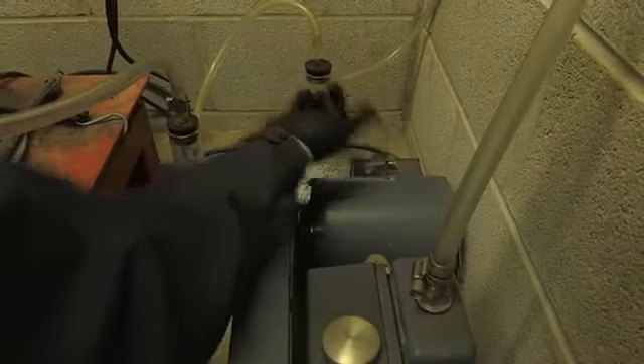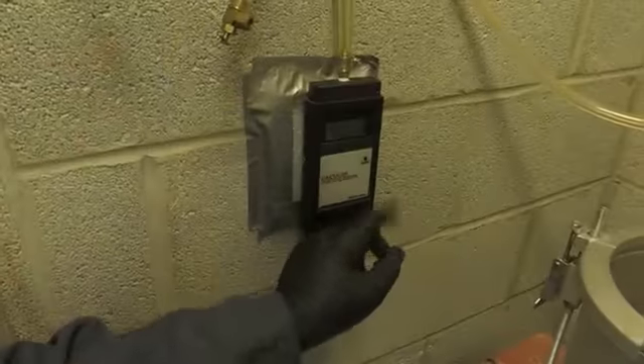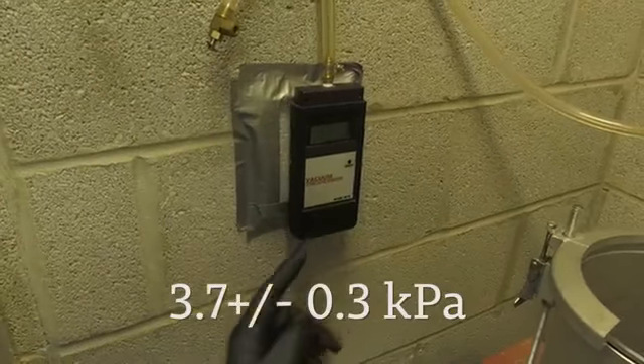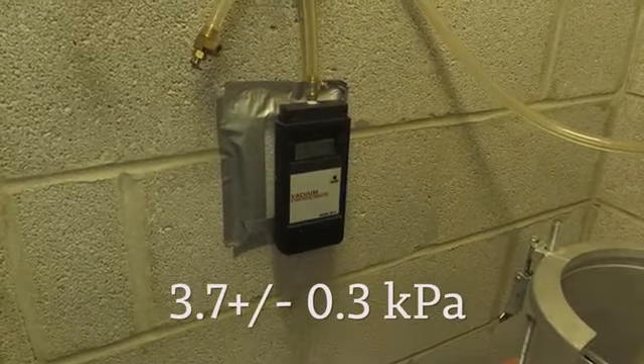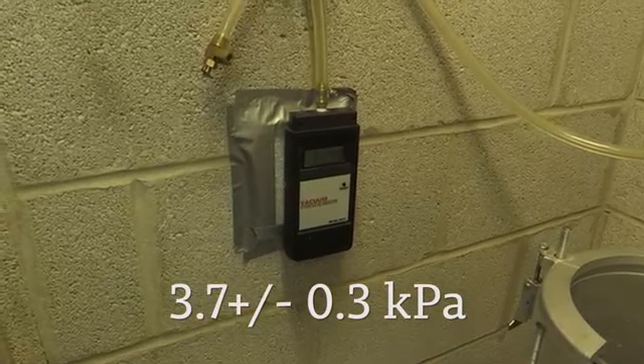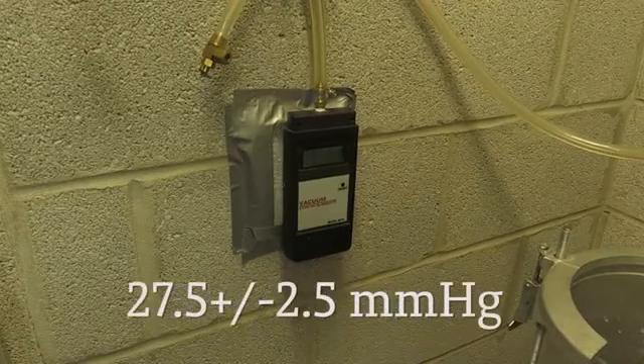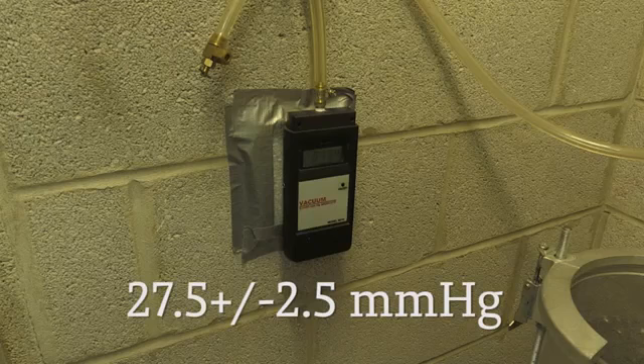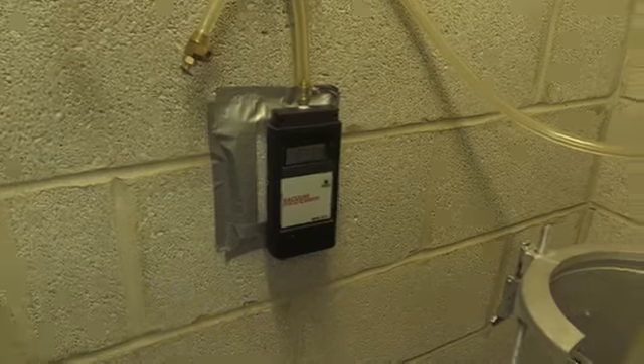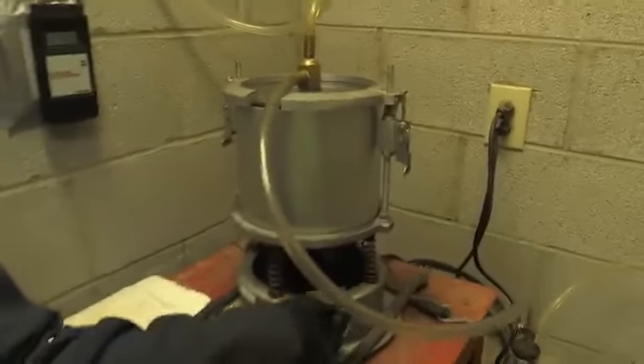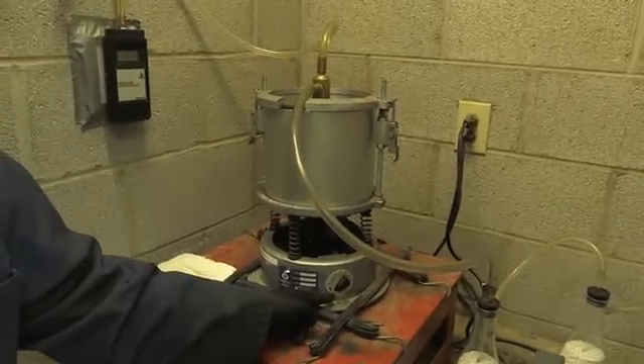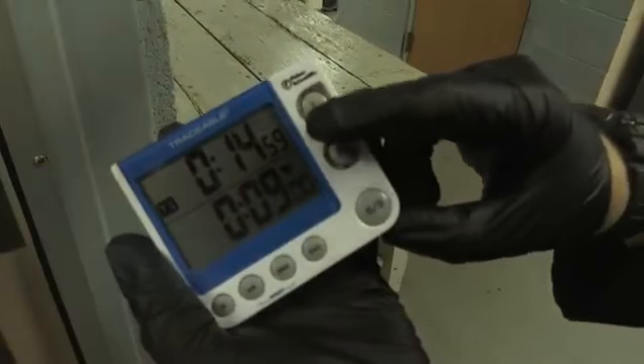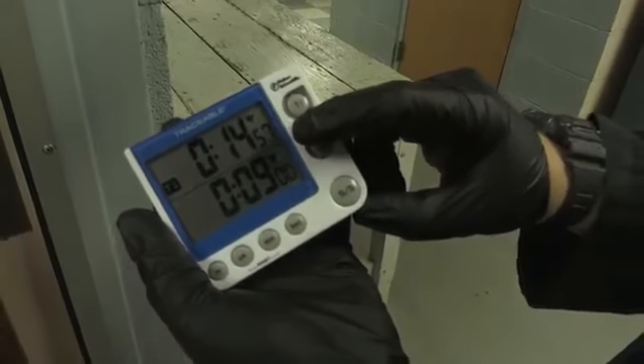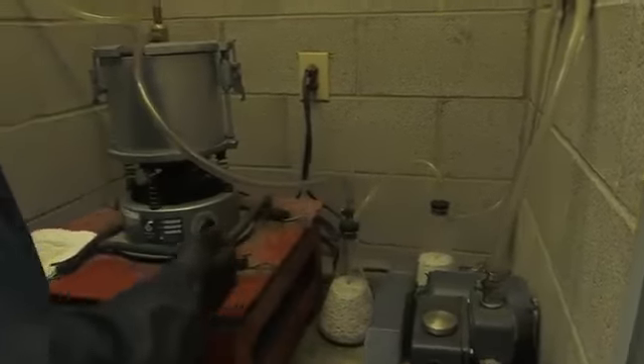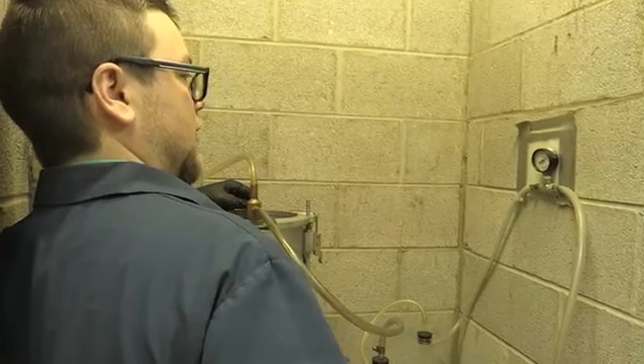Start the vacuum process and monitor the pressure manometer until it reads 3.7 plus or minus 0.3 kilopascals or 27.5 plus or minus 2.5 millimeters of mercury. When that reading is reached, start the mechanical agitator and let the system run for 15 plus or minus 2 minutes. Turn off the vacuum and slowly open the bleeder valve, raising pressure.